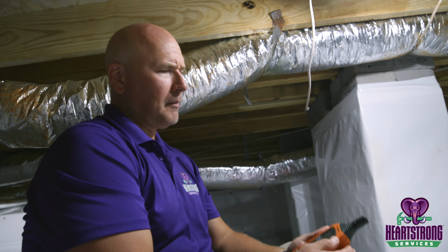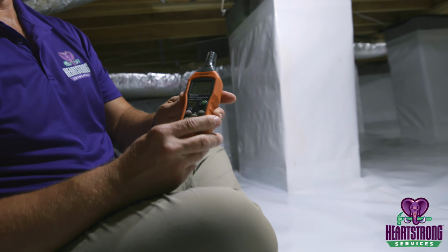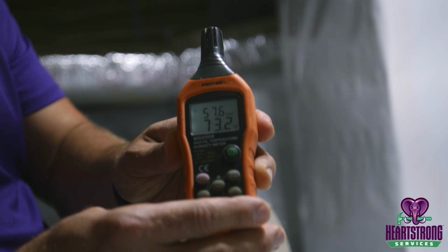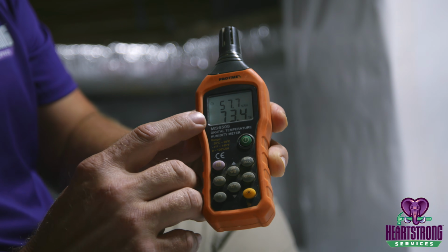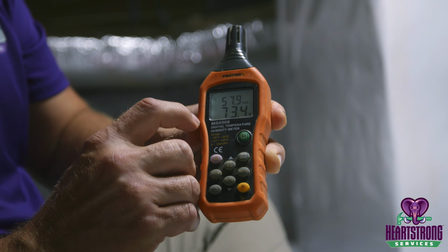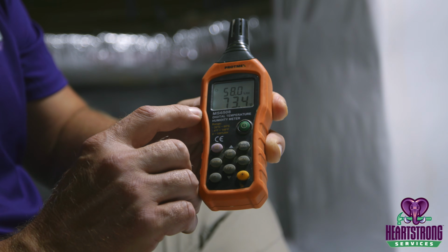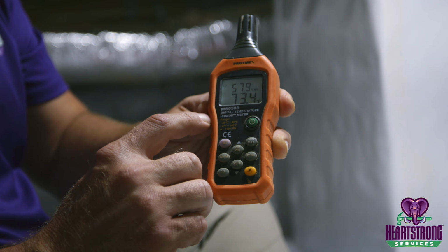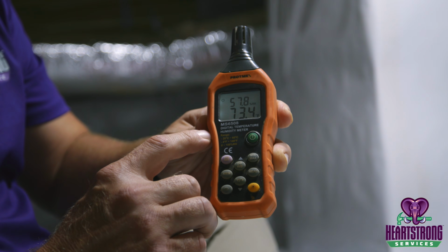if you remember in the previous video during the original inspection, we talked about what the temperature and more importantly, what the humidity was down inside the space. And I've got a device down here now so that we can see exactly where that's at. And let me light it up here to see if that makes it a little more visible. So what this is now currently showing us in this environment, the relative humidity right here at this meter is about 58% relative humidity, and it's about 73 degrees Fahrenheit. So you can see that there's a dramatic change.